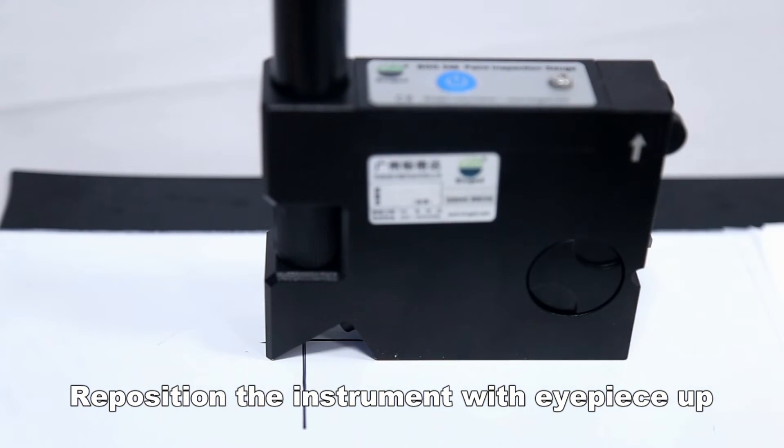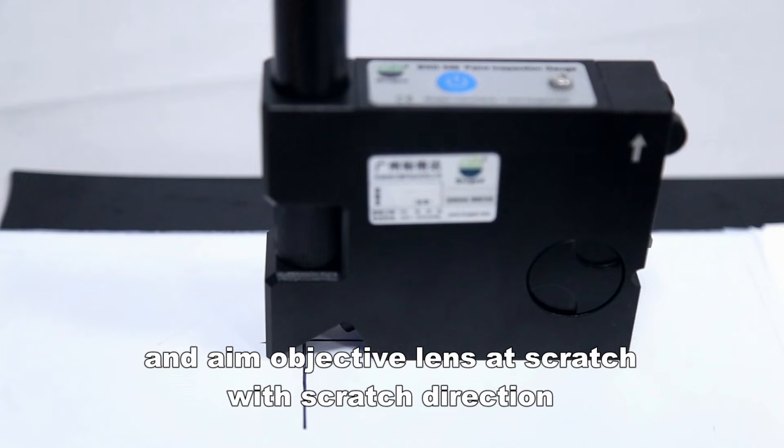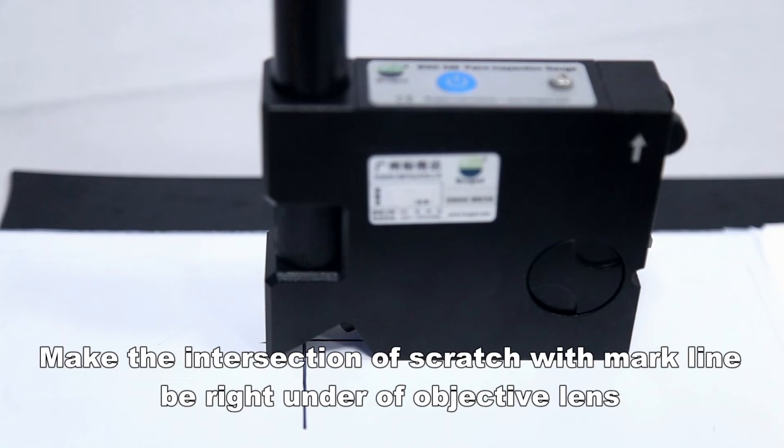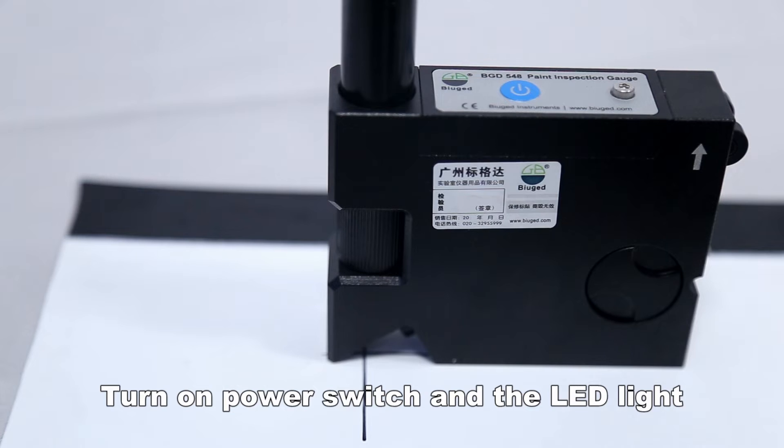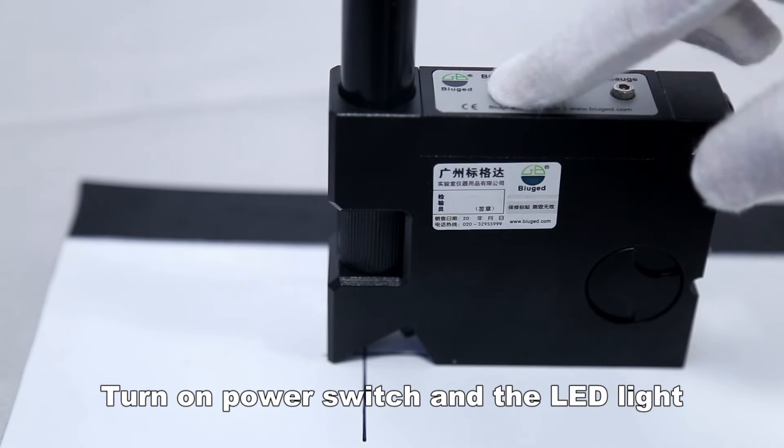Reposition the instrument with the eyepiece up and aim the objective lens at the scratch. Make the intersection of the scratch with the marked line be right under the objective lens. Turn on the LED light power switch.